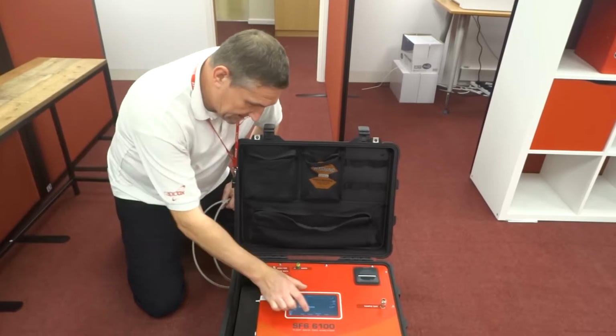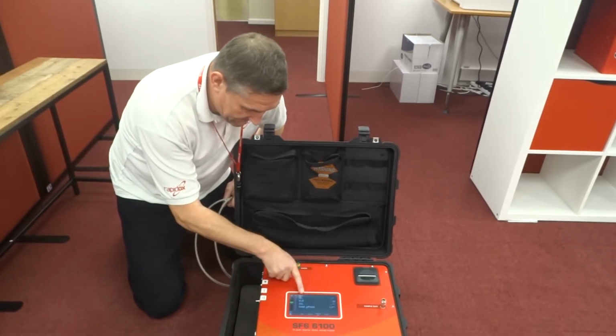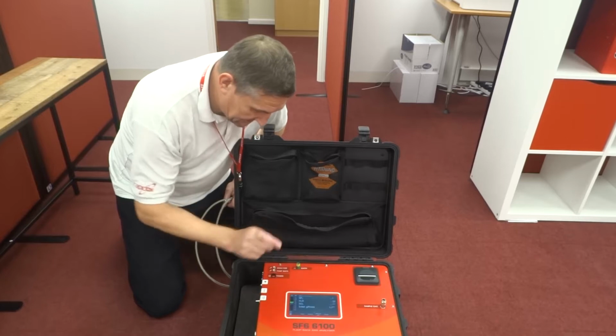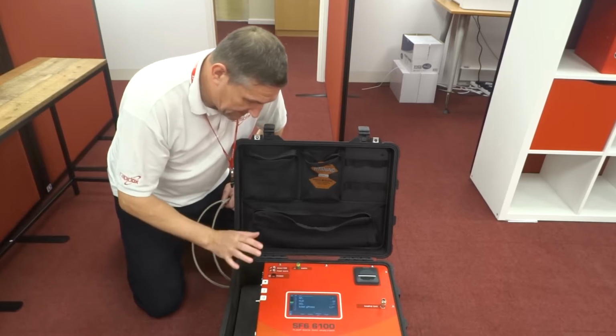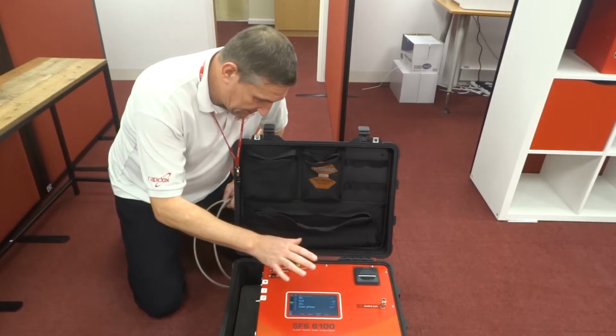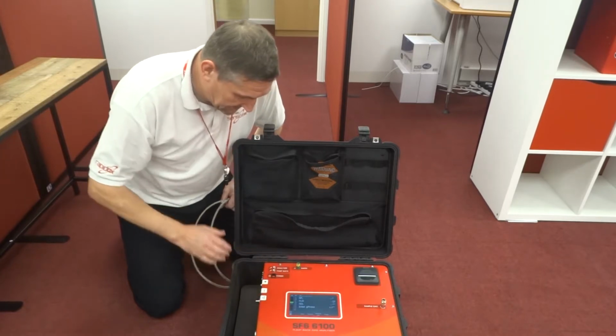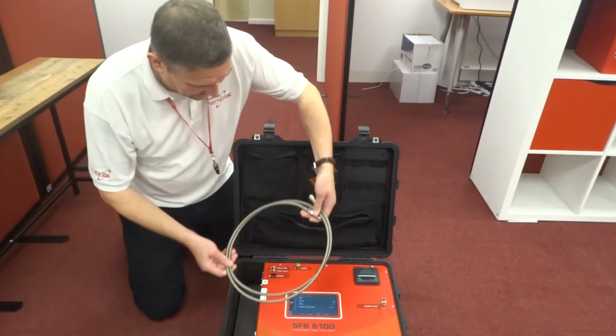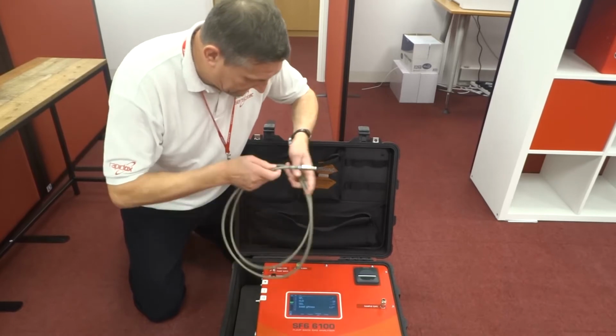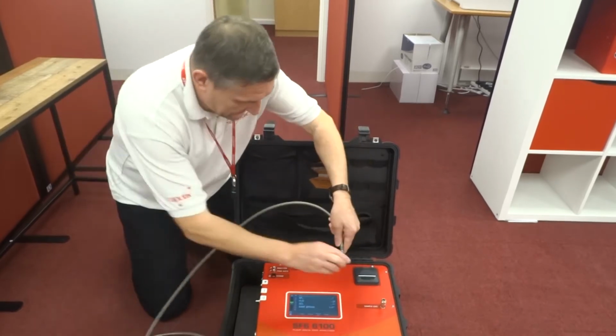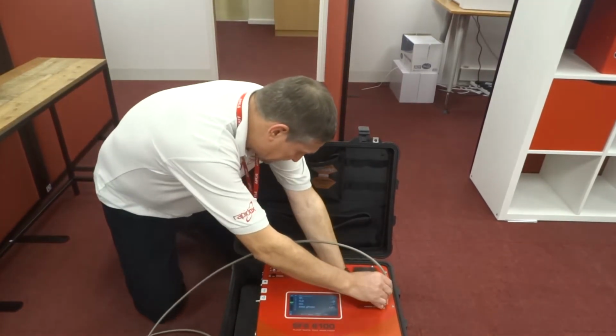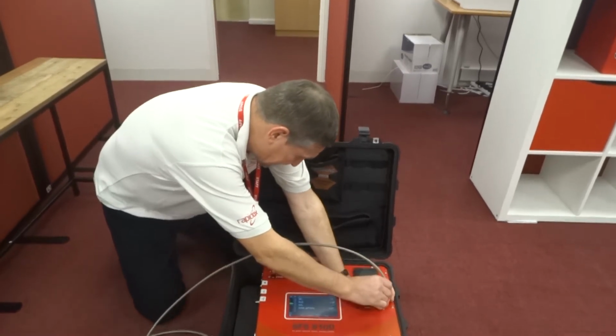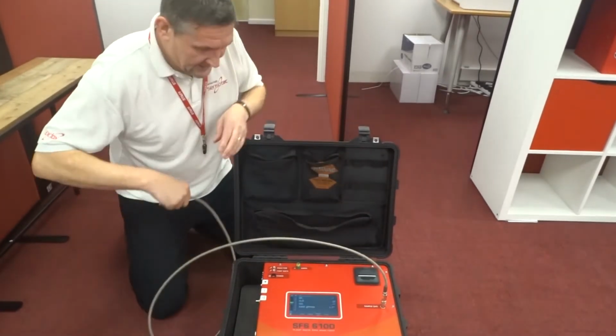Okay, so here's the main panel with the values of SF6, and I'm going to do the line purge first and then we'll talk about the measurements. It's very important with the measurement hose that this is connected to the analyzer like so. I shall push the collar down with my fingers and install.